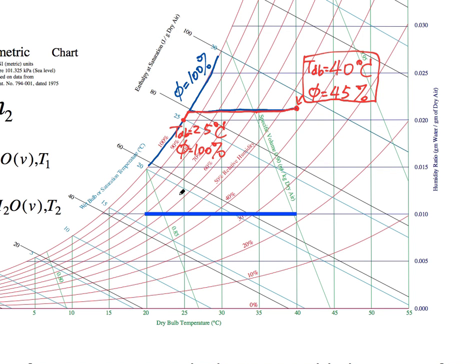So this analysis shows my intention to cool this moist air from 40 degrees, 45 percent relative humidity to 25 degrees without water condensation. That initial intention was not possible. That's not realistic. I cannot accomplish it in reality. So what I can do is I'll have to cool the air while dehumidifying it in order to reach 25 degrees Celsius. And this is often what happens in air conditioning, especially in cooling. So we need to not only cool the moist air, but also dehumidify the moist air when we refrigerate it. And we'll talk about this more when we deal with real air conditioning processes.